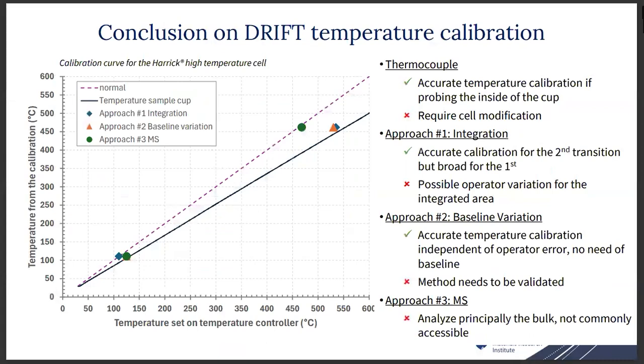So if I summarize everything compared to our temperature probe, the thermocouple in the bed, and the parity line, we can see 2 points that agree pretty well with the line, and the 2 points that most accurately represent the drift are the ones using the second approach. So this is a good way we could calibrate the temperature for the FTIR accessory.